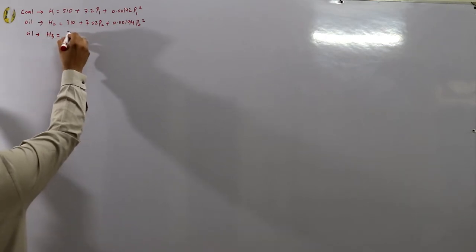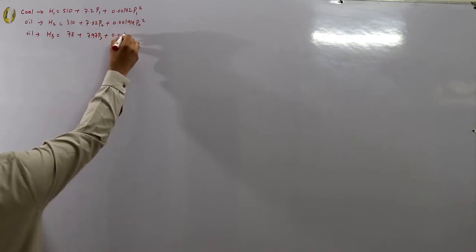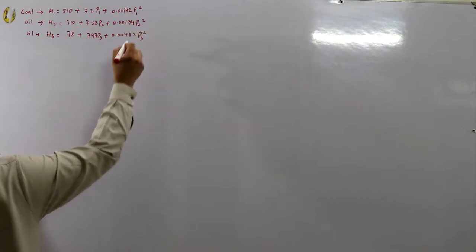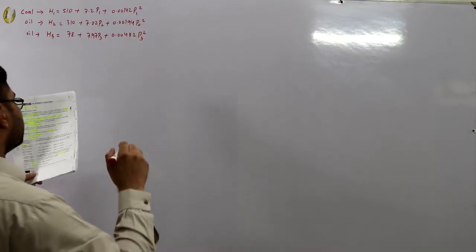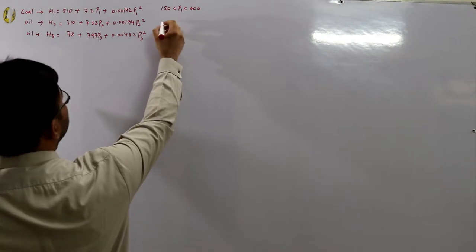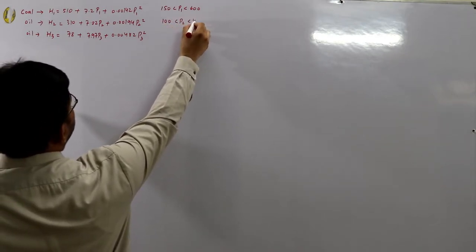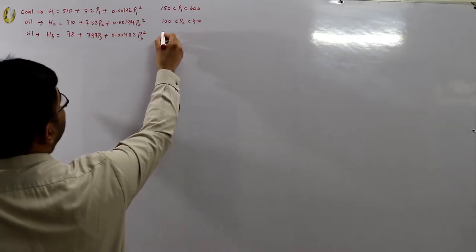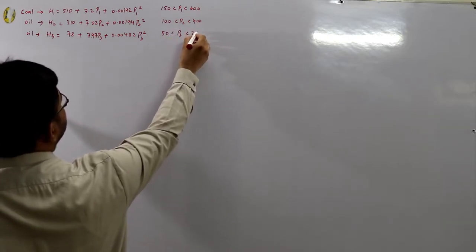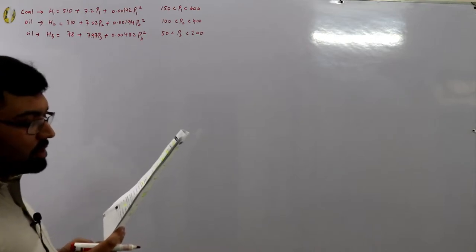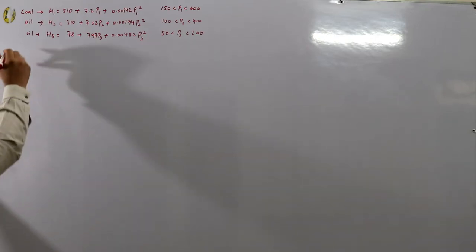Unit three is also an oil-fired station with cost model h3 = 78 + 7.97·p3 + 0.00482·p3². The optimal power dispatch limits are 150–600 MW for unit one, 100–400 MW for unit two, and 50–200 MW for unit three. Calculate the optimal power generated by each unit supplying minimum cost to a load demand of 850 MW.